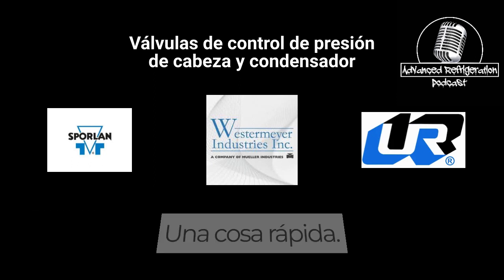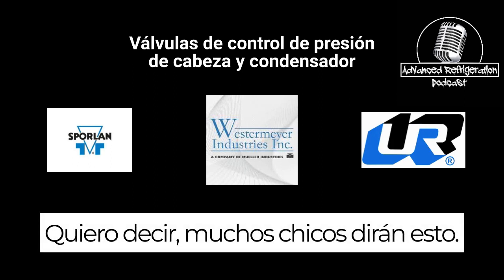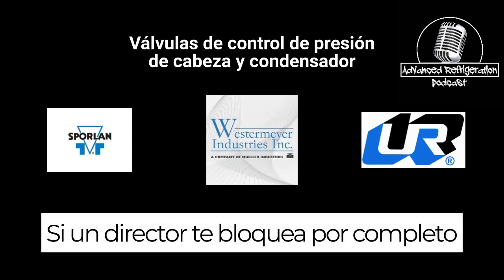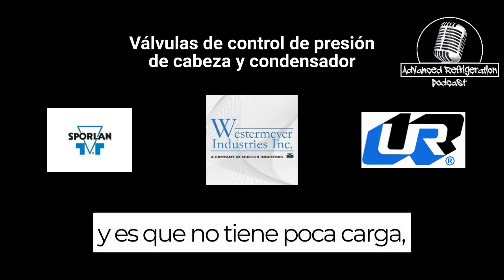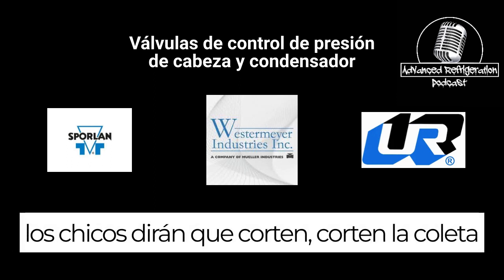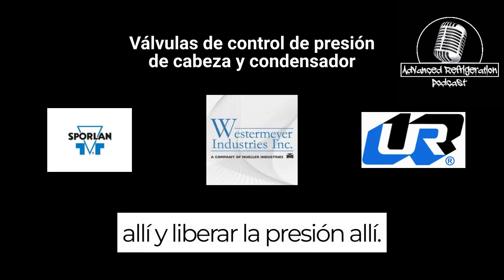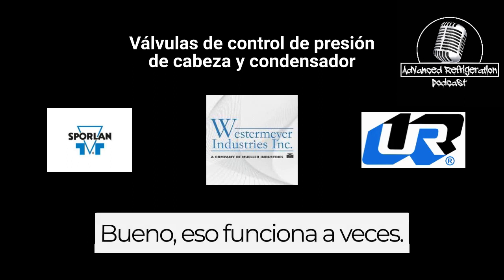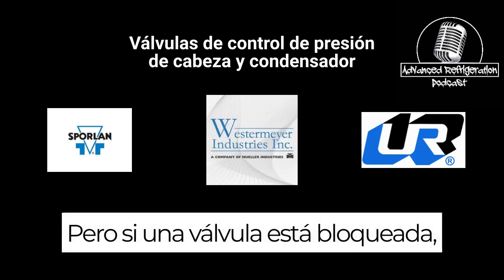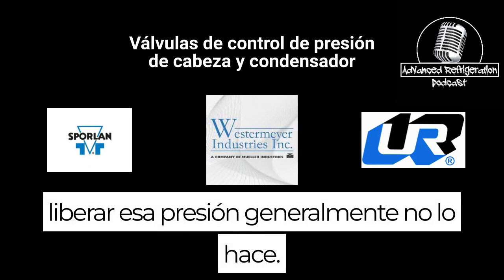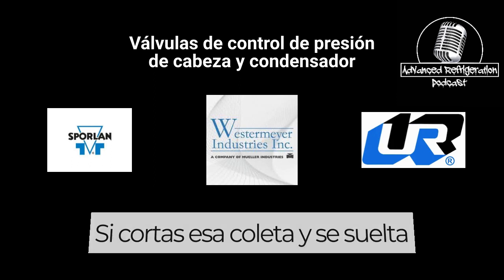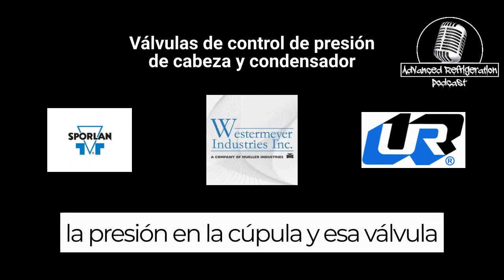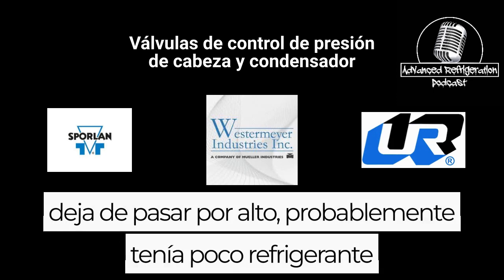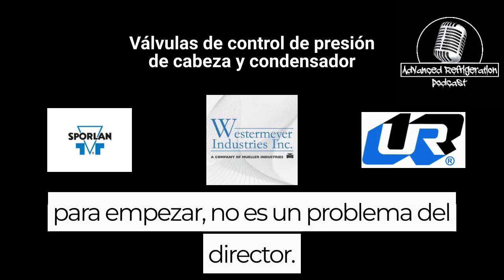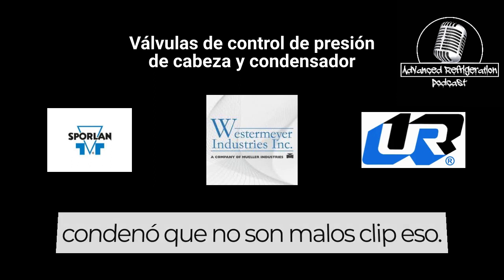One quick thing, a lot of guys will say this: if a headmaster does lock up on you completely, and it's not low on charge, guys will say to clip the pigtail off there and release the pressure in there. Well, that works sometimes, but if the valve's locked up, releasing that pressure usually doesn't do it. If you cut that pigtail and it releases the pressure on the dome and that valve stops bypassing, it was probably low on refrigerant to begin with. Not a headmaster issue. I see a lot of headmasters get condemned that aren't bad.